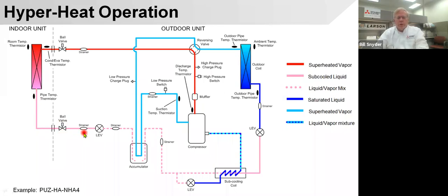There's another strainer, an LEV, which stands for linear expansion valve. It's an electronic expansion valve is what that is. And then another strainer, both sides of this. So no matter which direction the refrigerant's flowing, we're going to pick up something and try to protect. If there's anything in the line, we're going to pick it up at the strainer and try to protect the LEV.